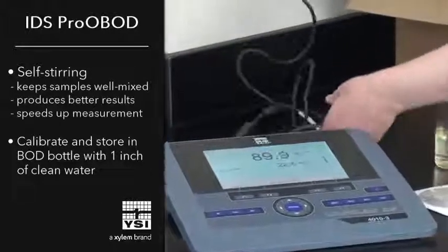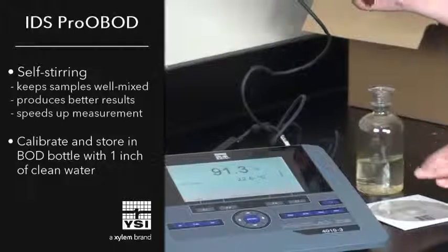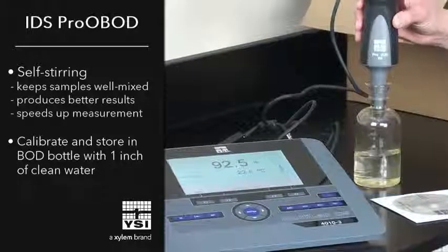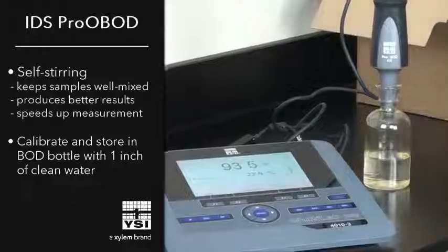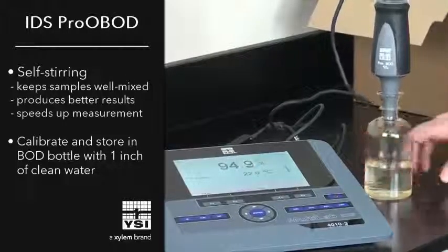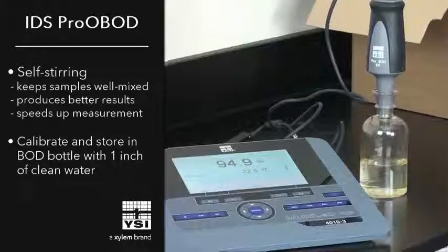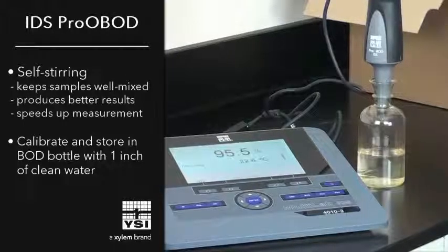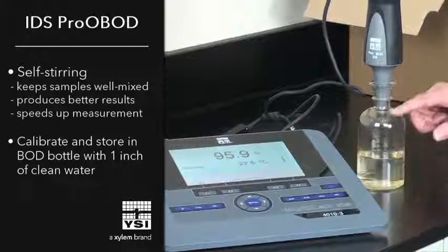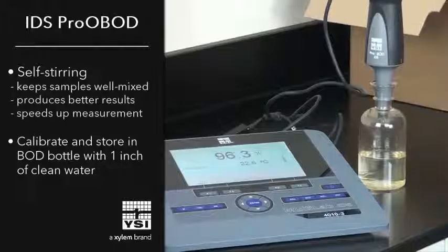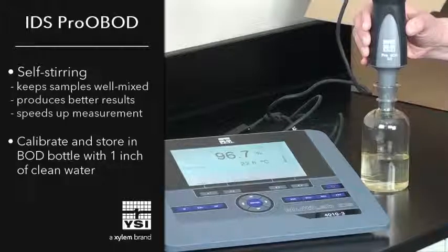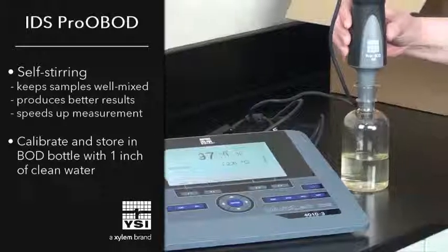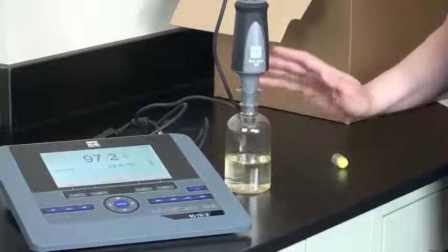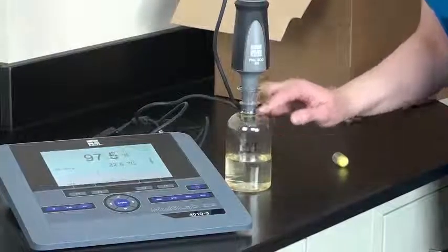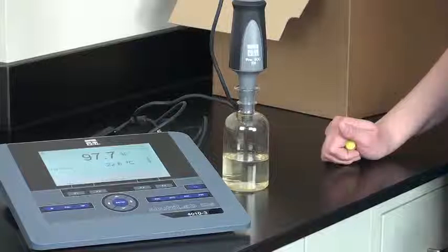To calibrate and to store the ProOBOD, simply place it in a clean BOD bottle with about 1 inch of clean water. And we're going to calibrate to the water saturated air above the water. After placing the ProOBOD in the 300 milliliter BOD bottle, wait about 5 to 10 minutes for this chamber to become completely saturated.